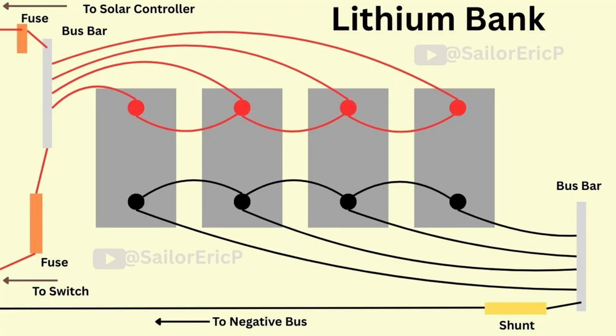This design is the recommended design by the manufacturer according to the manual. The solar controller provides a charge through a fuse to the positive bus bar, and a large 225 Class T fuse connects to the positive bus bar and then to a dedicated house bank switch. I also have a shunt installed on the negative side for the benefit of the battery monitor.